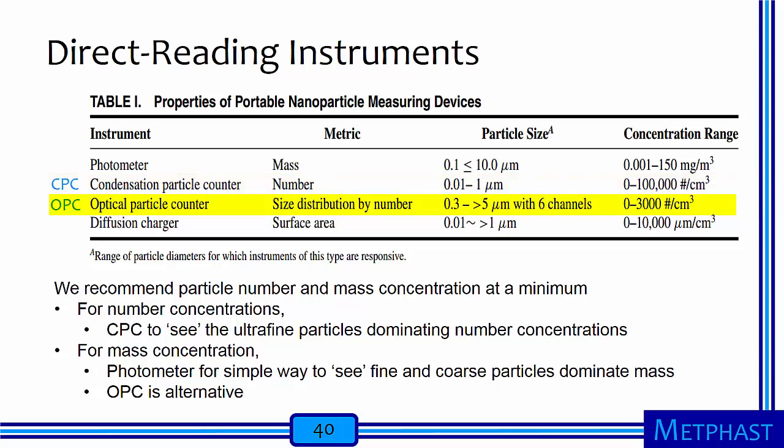The optical particle counter yields a size distribution by number from approximately 300 nanometers to about 5 micrometers in different numbers of size bins; typically, lower cost units have 6 size bins. The concentration range is much lower than for the CPC, but this device cannot see nanoparticles that have the highest number concentrations. Lastly, diffusion chargers provide a direct output of surface area concentration of sub-micrometer particles, though these instruments are uncommon in today's industrial hygiene practice. We emphasize the use of instruments that provide the ability to see particles across a wide range of multiple metrics. The condensation particle counter provides the ability to see ultrafine particles dominating number concentrations, while a photometer is a simple way to account for fine and coarse particles dominating mass concentrations.